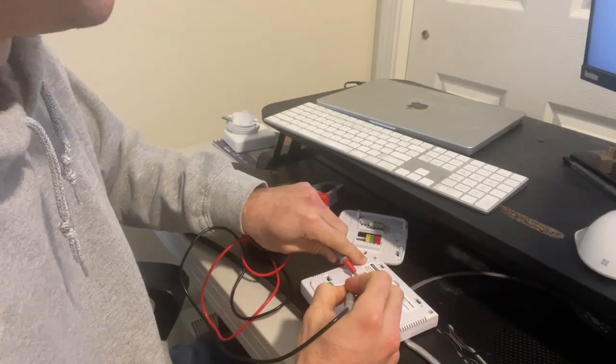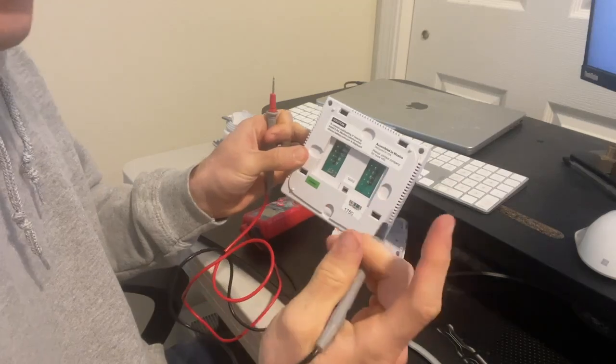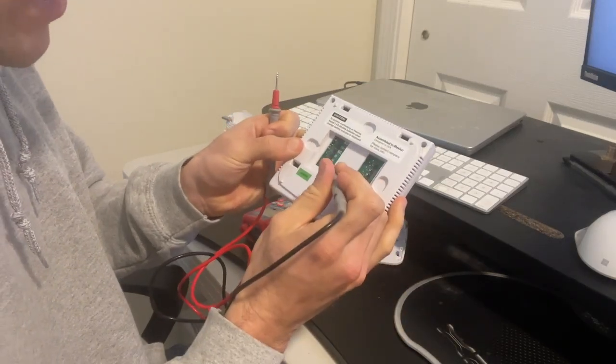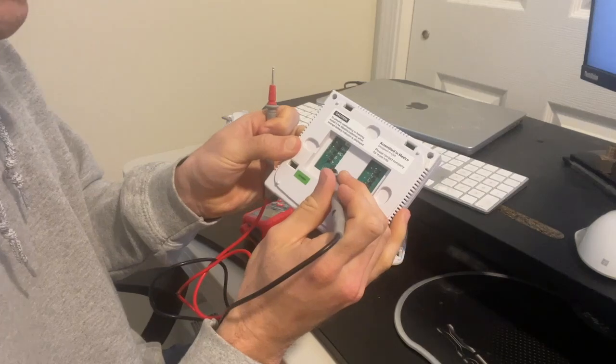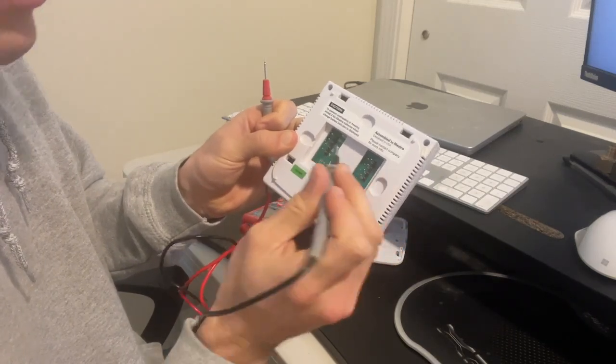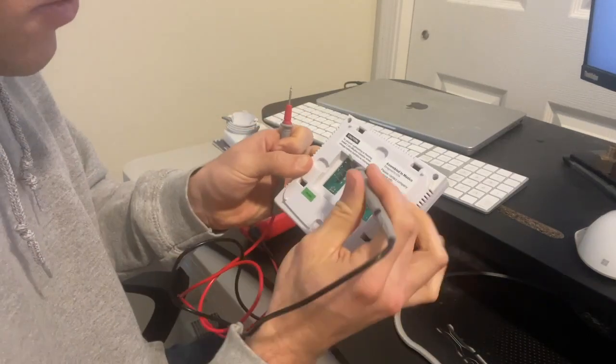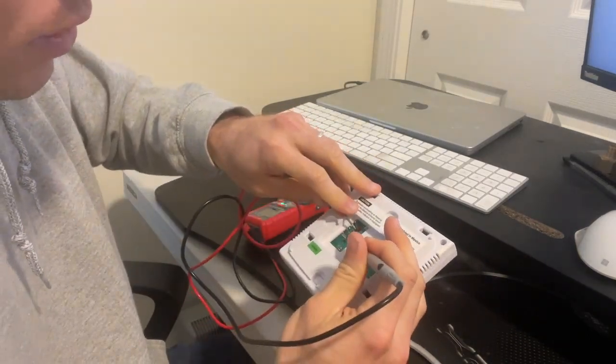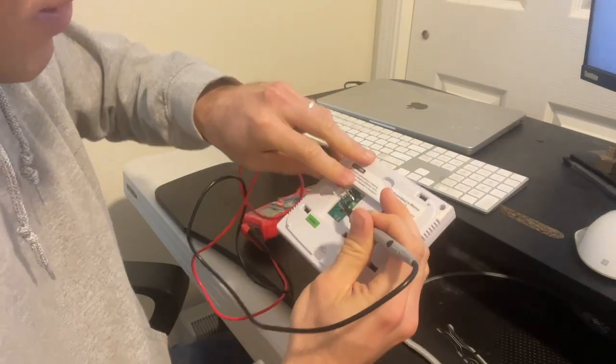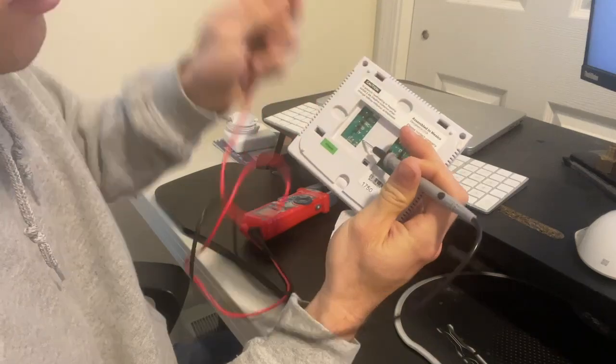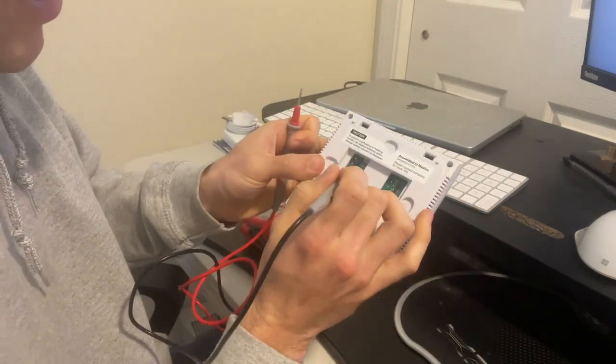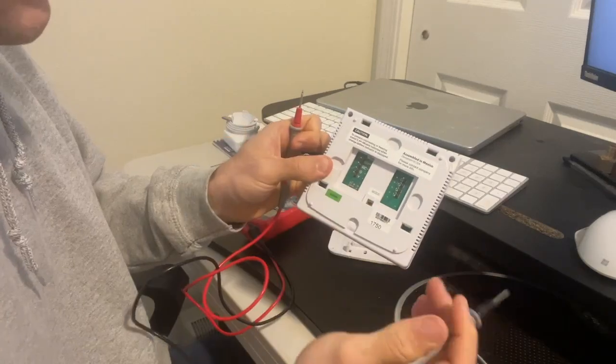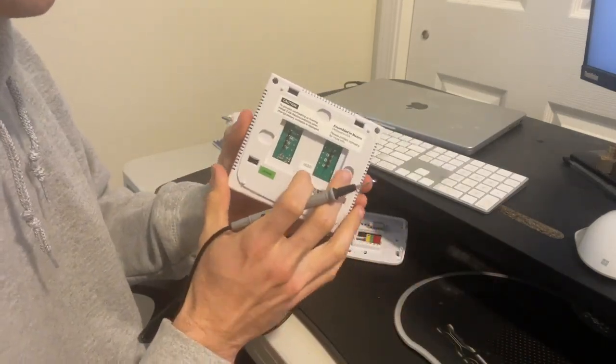And then the other thing, when this thermostat is in cooling mode, is it's going to kick on the fan. So Y is the connector for the compressor and then G is for the fan. And so you should hear that continuity between RC and G as well as Y. And so if you don't, then that tells you that this thing's faulty and you should replace it.